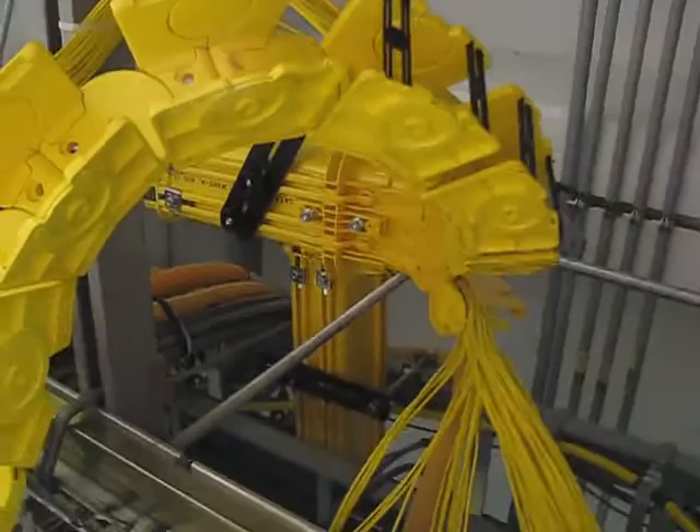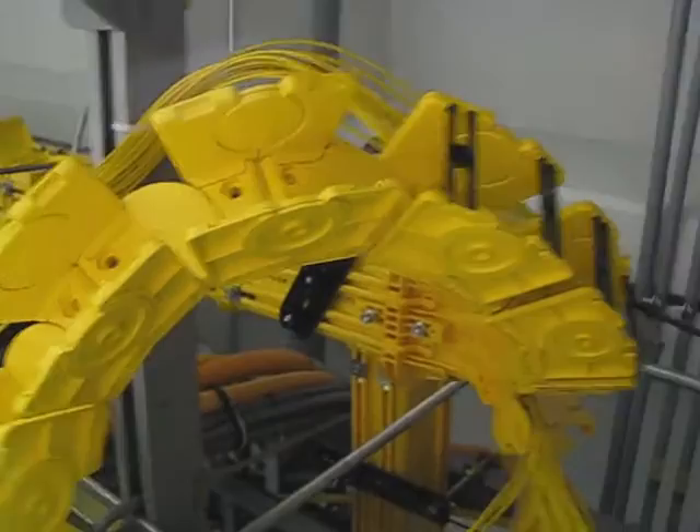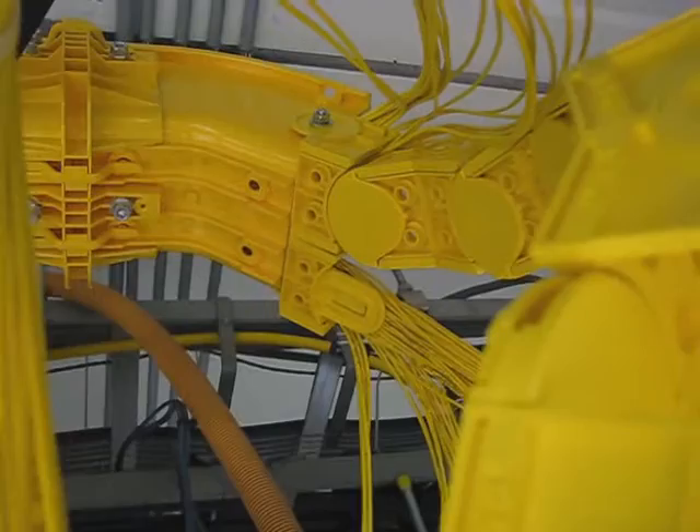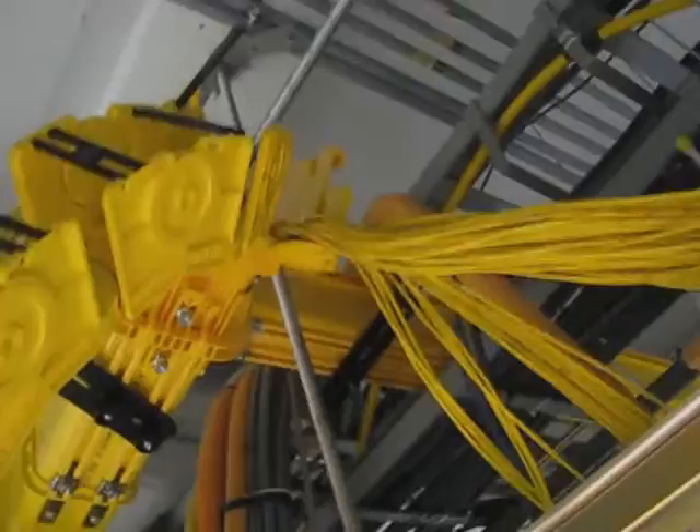Here's one of my preliminary solutions — using these two inch by two inch flexible telec fiber troughs being fed from a 45 degree angled horizontal trough connection, with two telec pieces bolted to it and bolted to each other. So I'd have one feeding one side of the FTP and one feeding the other.